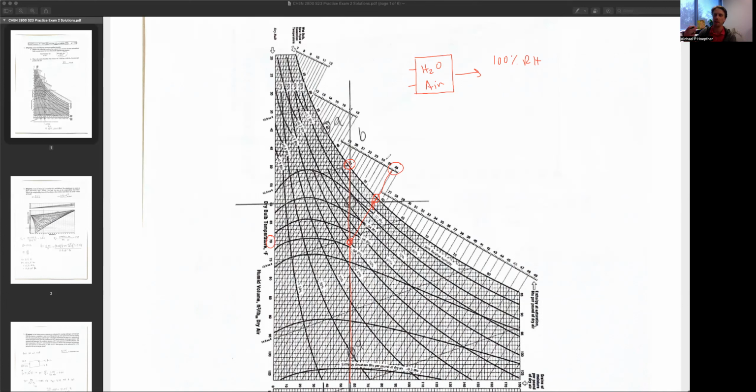All of the energy that goes into evaporating the water is cooling off the thermometer, and the total enthalpy of the system stays the same. So you cool down the thermometer, and that energy is taken away by those water molecules evaporating. That's why the wet bulb temperature follows a line of constant enthalpy. I was very worried that I had been misleading everyone about how to read the psychrometric chart. I was teaching the chart correctly, but I was not clear on my own side about the rationale behind its design.